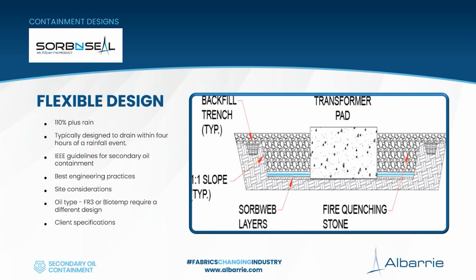If the oil is not mineral—for instance, a synthetic ester or a natural ester oil—the design looks somewhat similar, but the layers may differ, and the polymer would definitely be different, because we need to match the chemistry in the polymer, which has a specific chemical chain, with the chemistry in the oil, which has a different chemical chain. Mineral oils are hydrocarbon based, so their chemical chain differs from natural ester oils, which aren't derived from hydrocarbons. We need to make sure those two things are compatible, so again we follow your specifications if you've developed them for your unique project.